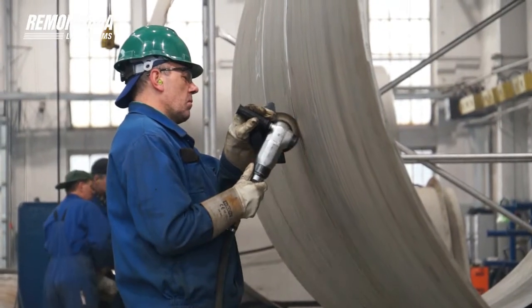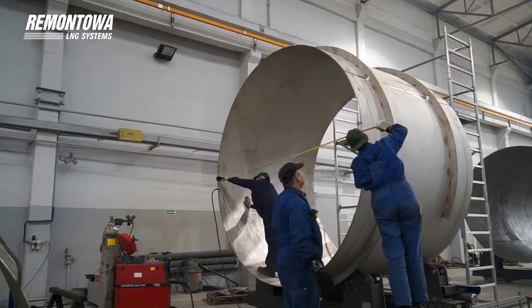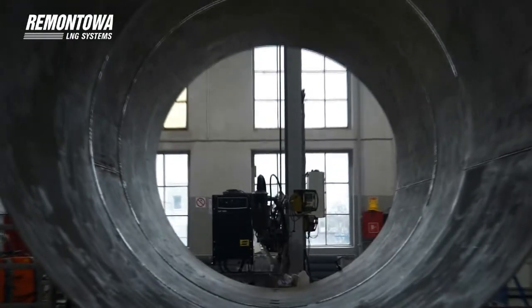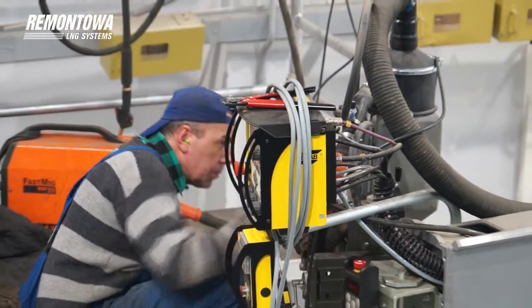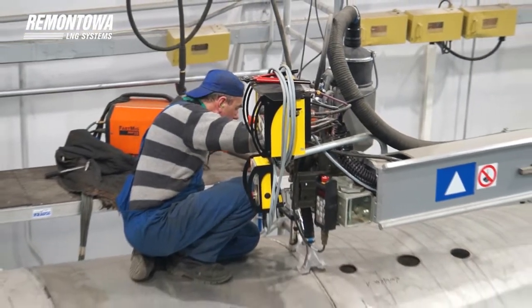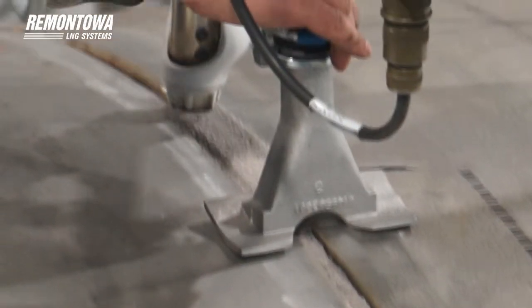The LNG fuel tank, due to low operating temperatures, consists of two shells, an inner tank used as a cryogenic vessel and an outer shell used as a vacuum vessel. The space between both tanks is filled with a non-toxic and non-combustible perlite used as insulation.